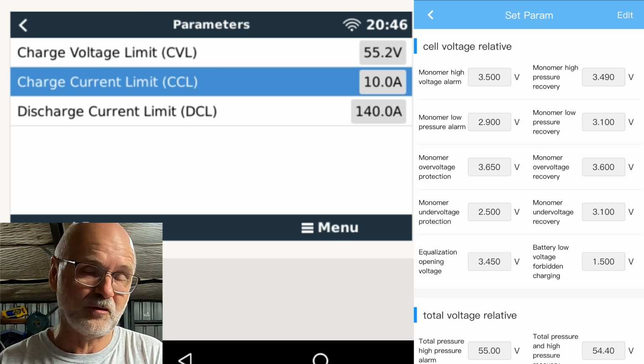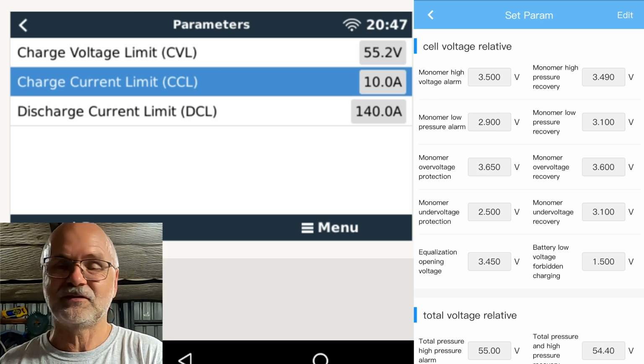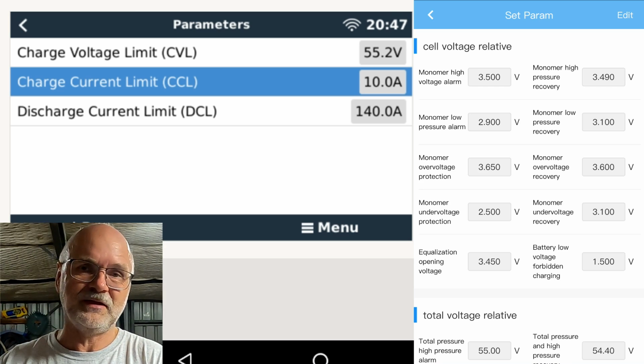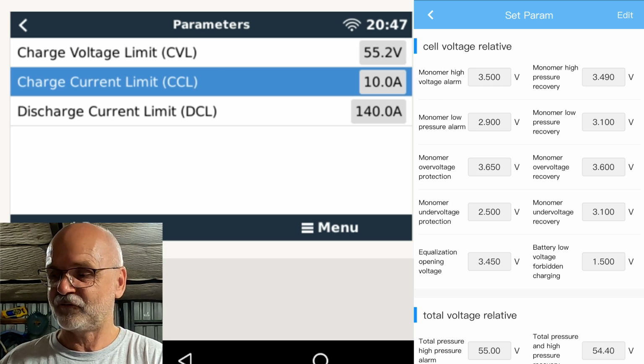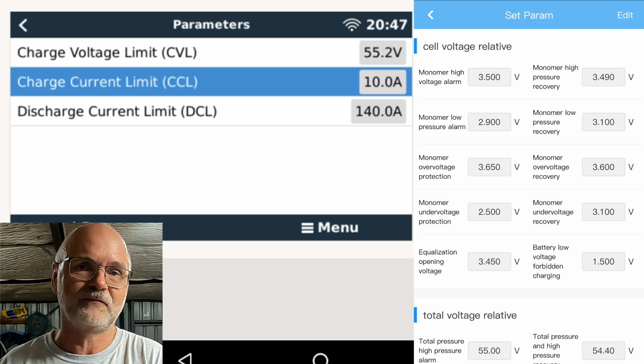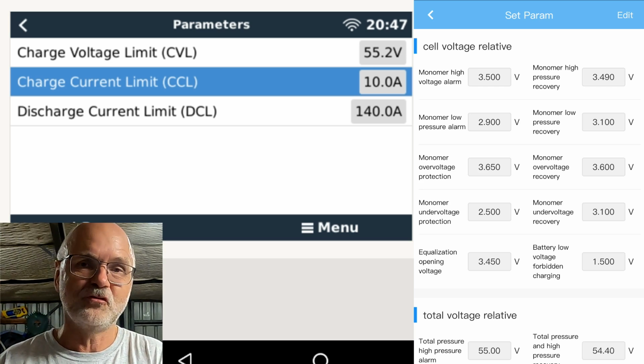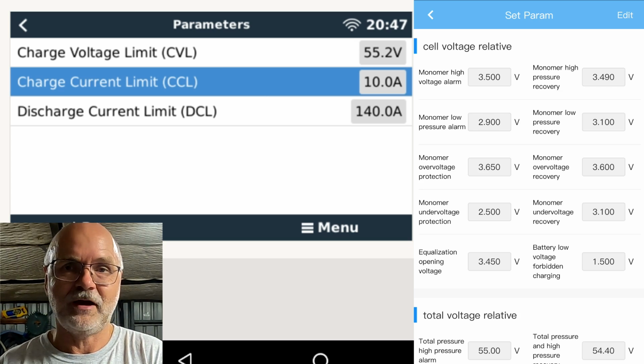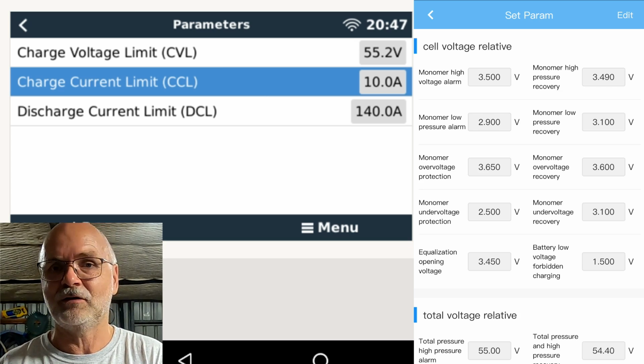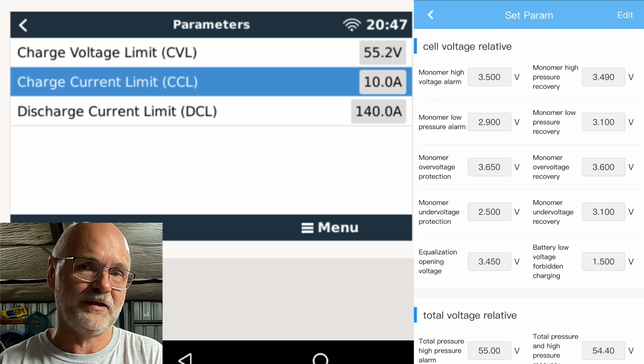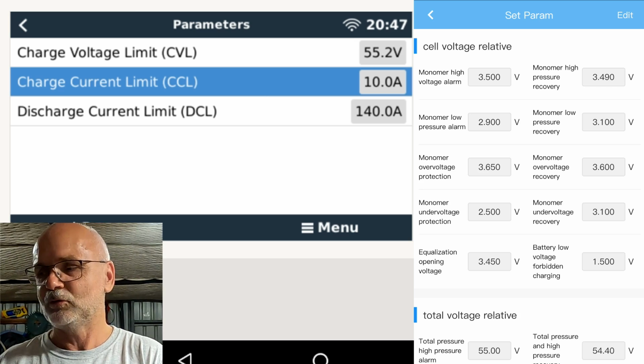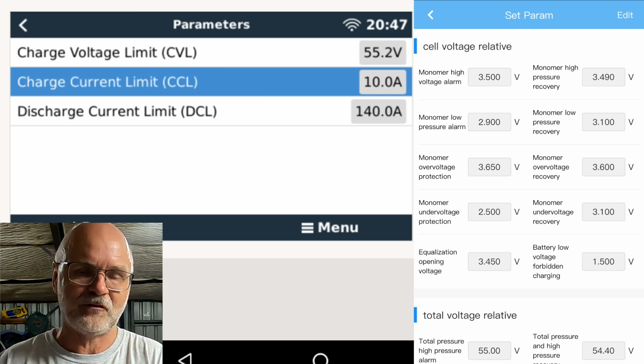This is different with lithium batteries, but again, I have the same issue here. My solar array is now in summertime far too large for these batteries, and the battery shelf is not designed to take 270 amps. So I have actually limited this current into the battery shelf to 200 amps only, because this is something which can be safely transmitted into the batteries.